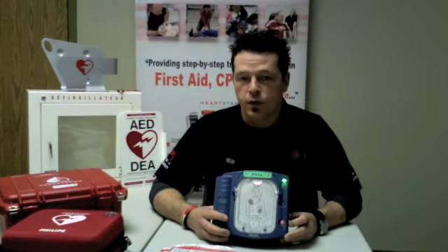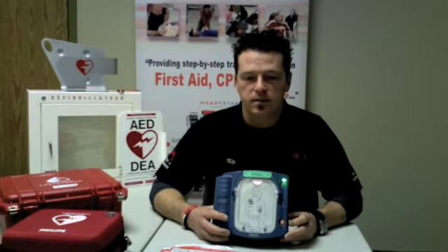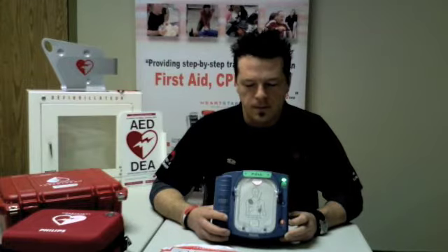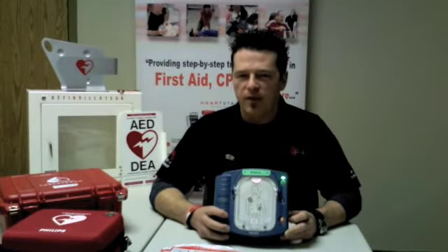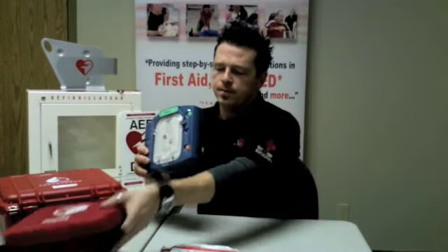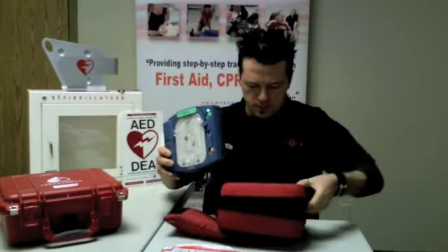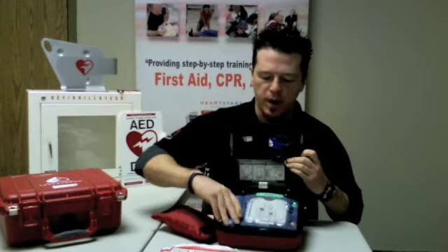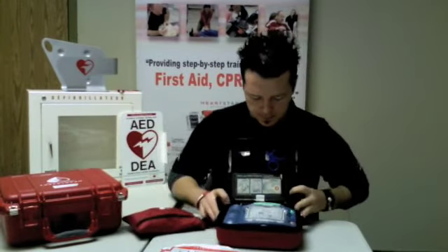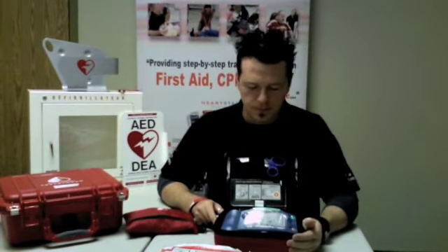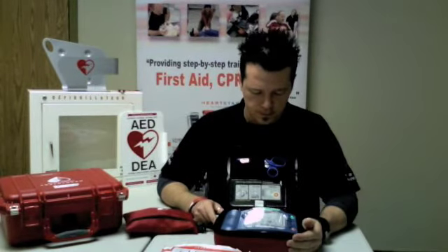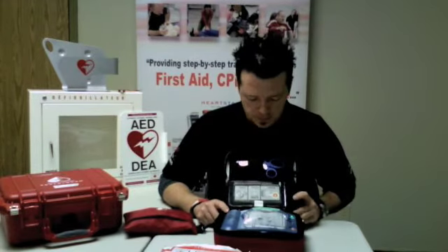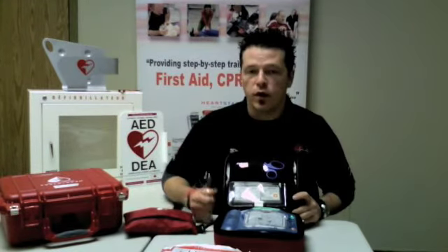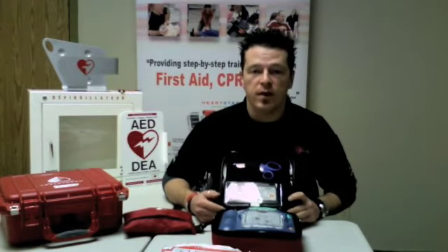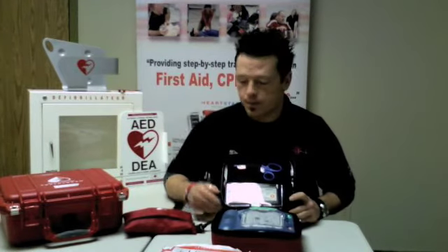Testing. It'll do this testing for about 1 or 1.5 minutes while you're waiting. Put the defibrillator back in. Testing. You will start to hear clicking sounds within the defibrillator. Testing. And at this point, you can move on to starting to make sure that the rest of the accessories are in good working order.